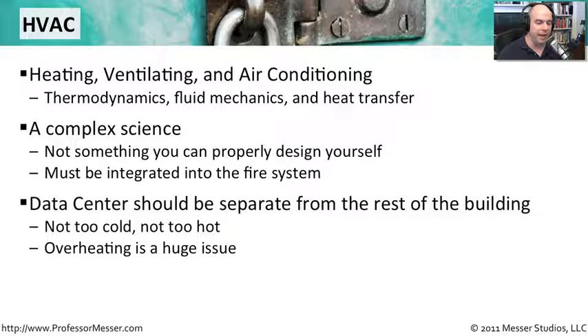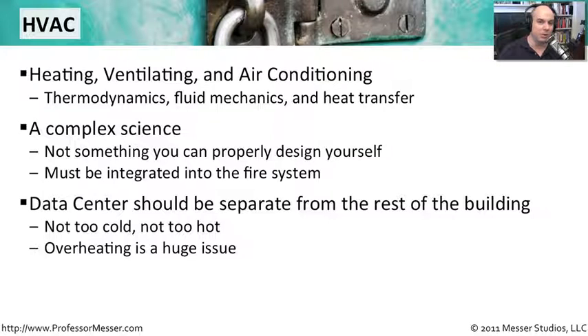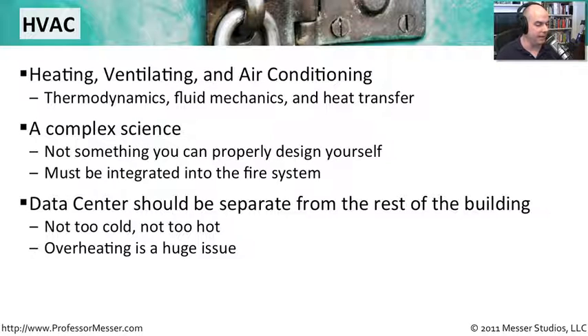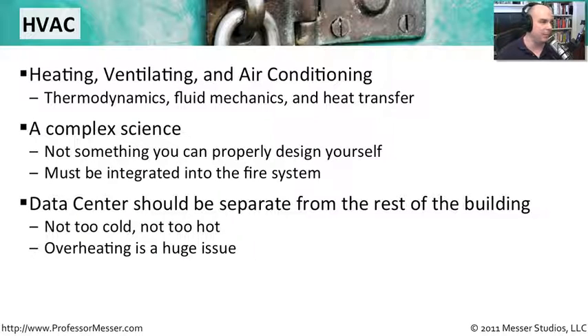Your data center should be absolutely separate — certainly from a heating, ventilating, and air conditioning perspective — from the rest of the building. The data center gets very hot. If you cooled the rest of your organization as much as you cool that room, everybody would be very, very cold. And if your people are cold, they'll change the temperature, which means the temperature in your data center would rise. So by keeping those separate, you can really maintain the proper amount of cooling and heating. One of the problems in a data center is overheating, so you want to be sure that if something were to happen to the heating or cooling system in other parts of the building, your data center would still be in perfect operating condition.